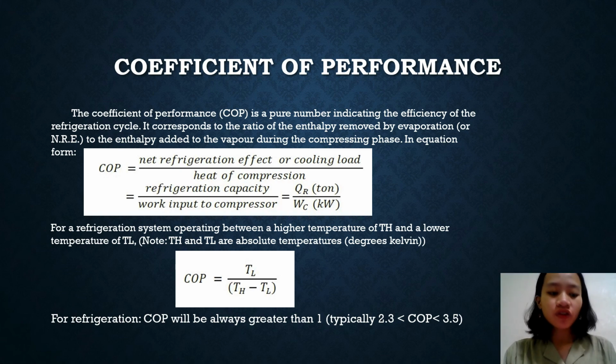The coefficient of performance of refrigeration systems varies according to the conditions under which they operate and the components constituting them. Therefore, it should not be used to compare the performance of two refrigeration systems that operate under differing conditions and or that are not entirely made up of the same components.